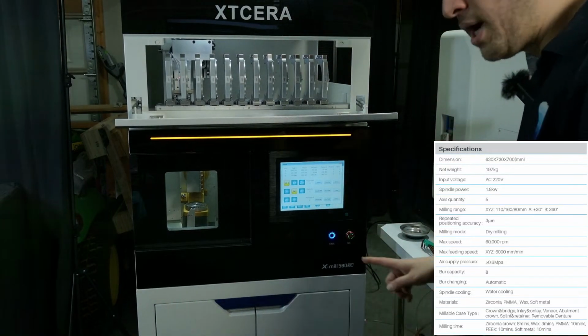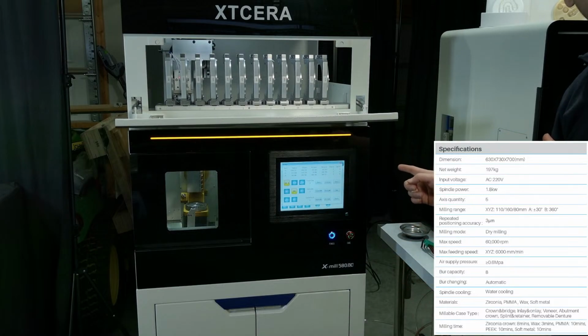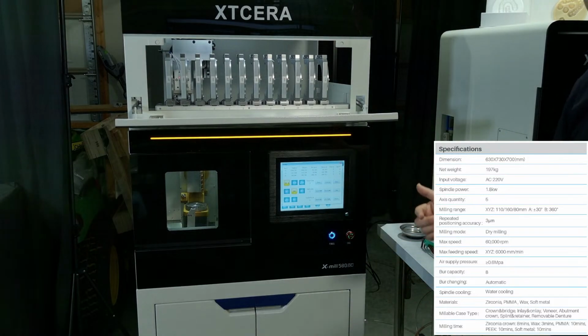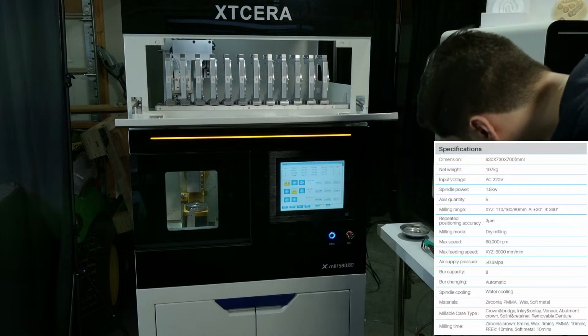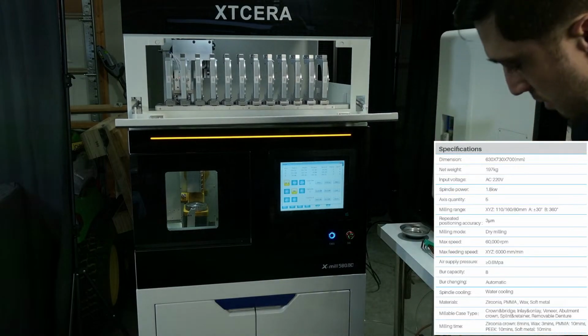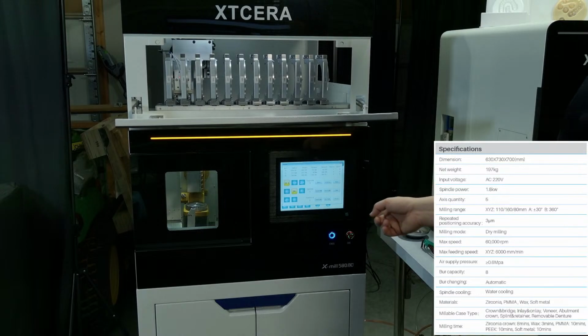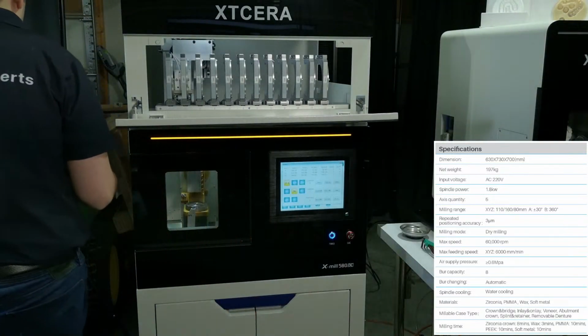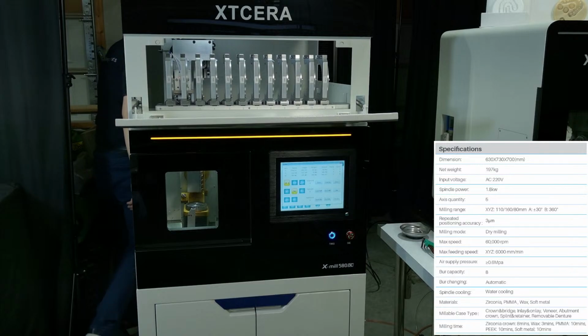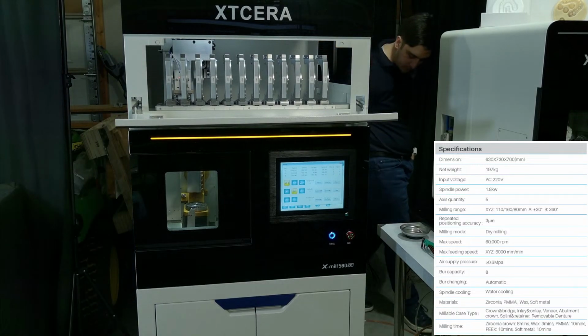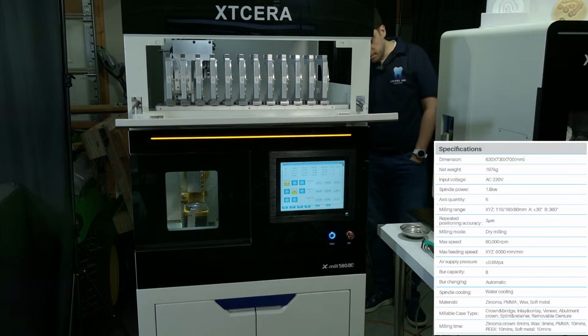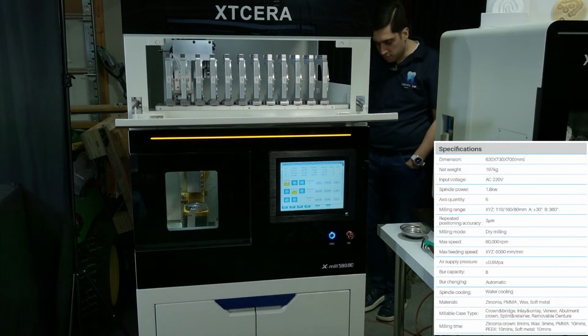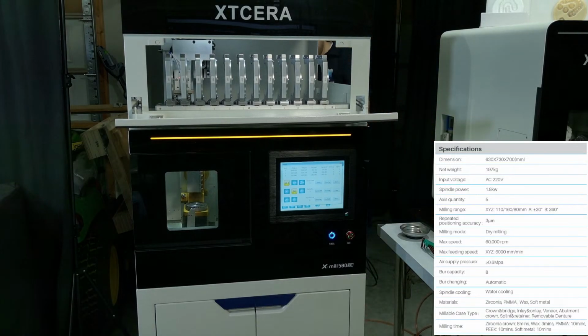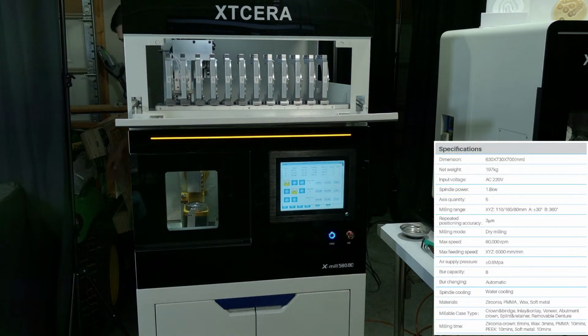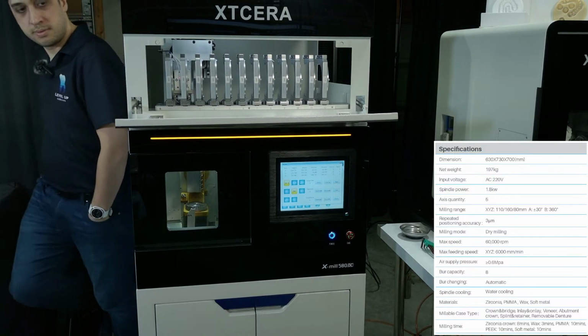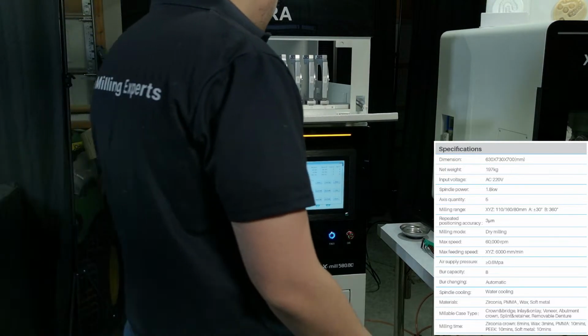Okay, I noticed that when I turn this on, the chiller didn't turn on automatically, and that's just because there's a power switch on the front of the chiller. So I'm going to flip that power switch. Chiller's now getting power. Now I'm going to go and double check my coolant lines, just make sure I'm not having any coolant leaking out. All right, and it just completed its first loop here. So the coolant is flowing through the machine and everything looks to be good there.